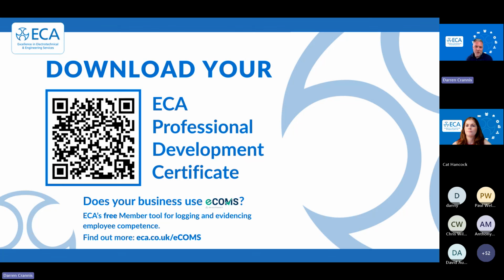Eddie's question, when RCD manufacturers state test regularly, what is regular? Open-ended question on that one, Eddie. I think typically we're talking guidance about every 6 months. And the reason for that is because your clocks change every 6 months. It might be a great idea to test your RCDs, but some manufacturers may state monthly. Often, as we know, it normally comes on a 5-year periodic inspection when you go and press the button and nothing happens. But 6 monthly is the guidance on that. Some manufacturers do state monthly.